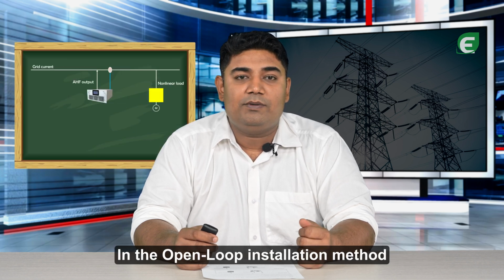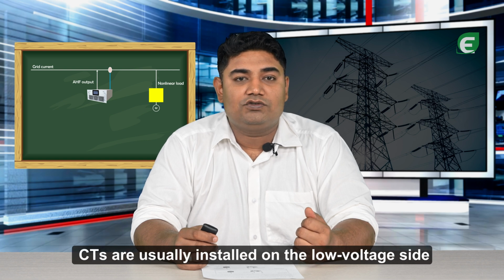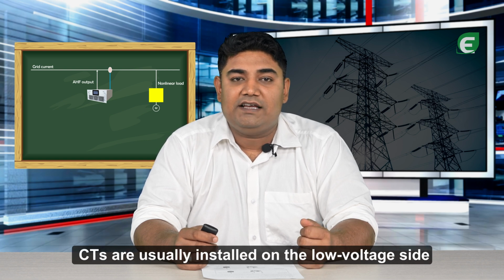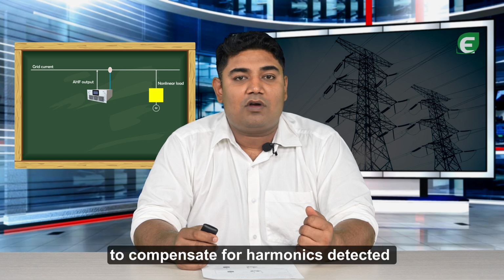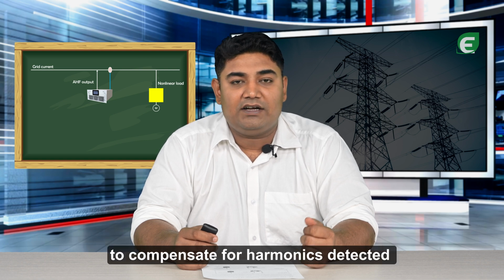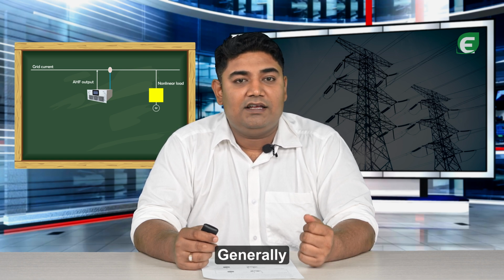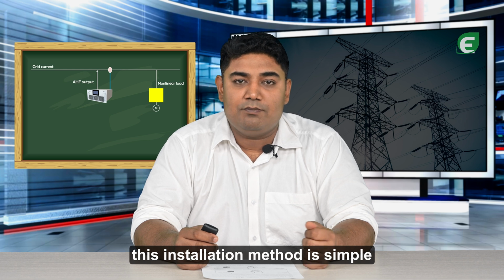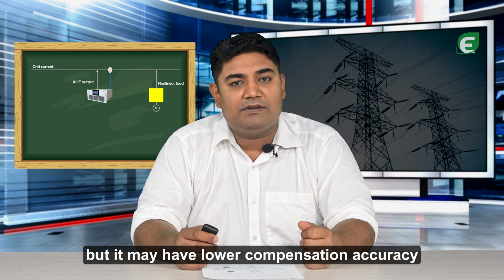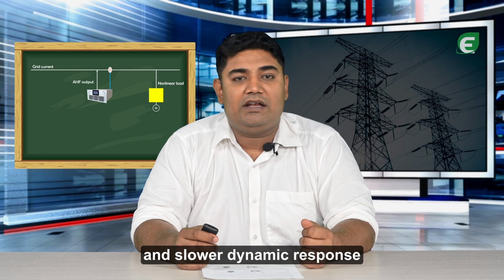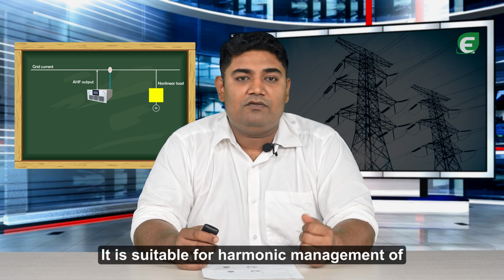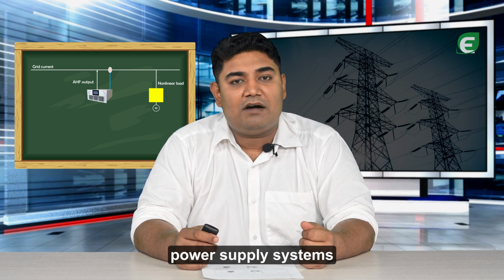In the open loop installation method, CTs are usually installed on the low voltage side of the distribution transformers to compensate for the harmonics detected on the power source side. Generally, this installation method is simple, but it may have lower compensation accuracy and slower dynamic response. It is suitable for harmonic management of power supply systems.